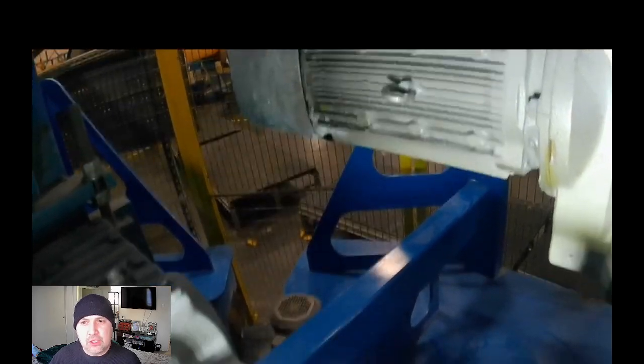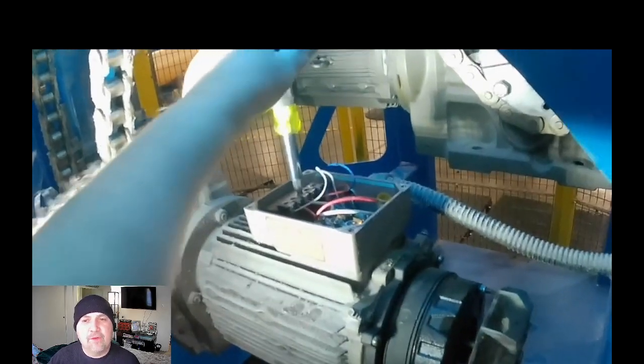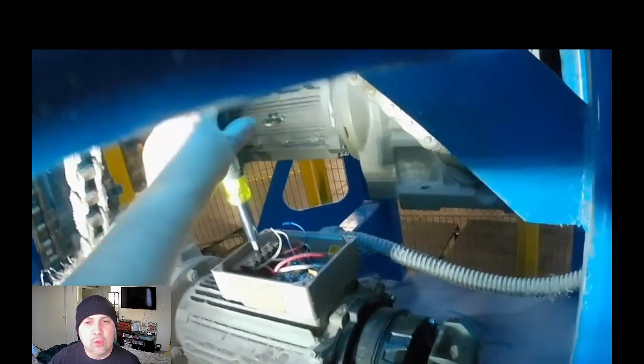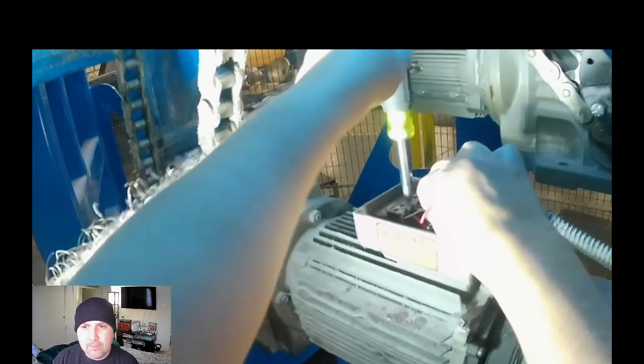So this motor seems like it wants to function, but something's holding it up, and I noticed right away that it has a brake. So I went to do a tug test on all the wiring, and I did find that one of the wires was loose. So I plugged that back in, and I was thinking, all right, cool. Wire's loose, no big deal. Let's get moving. Problem solved.